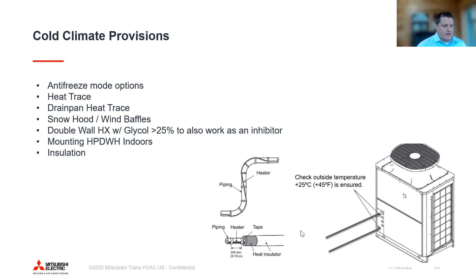Then the same provisions happen for the heat pump itself. You need to make sure it's above the snow line, have heat trace in the drain pan as well for the defrost sequence. Then just normal rules apply for insulation throughout the system.